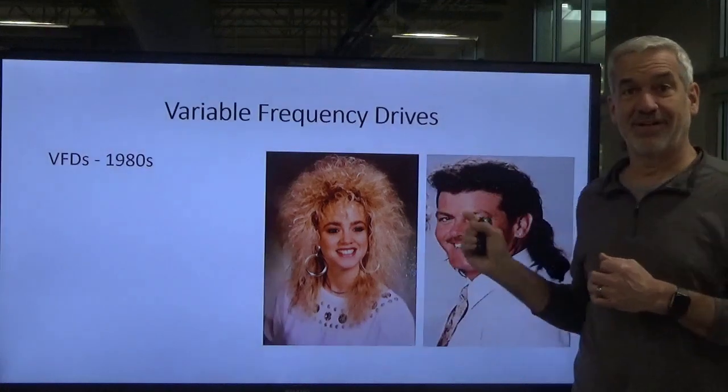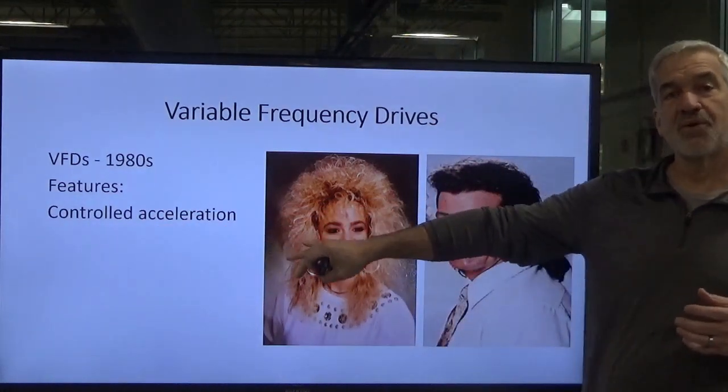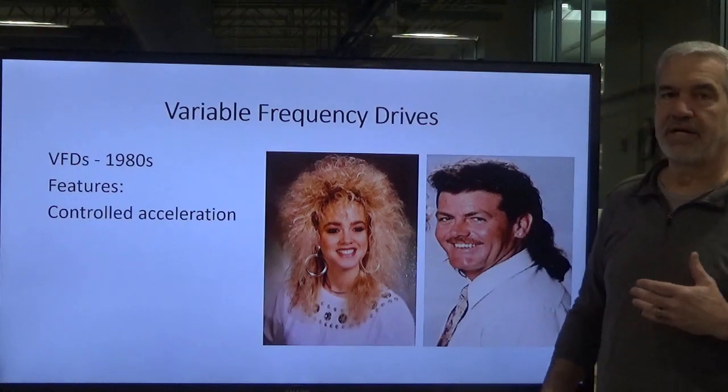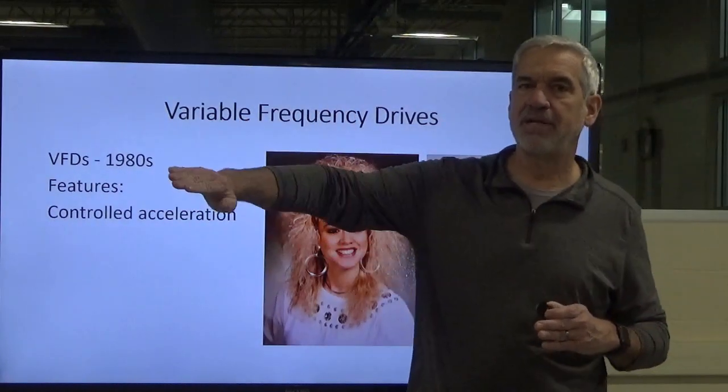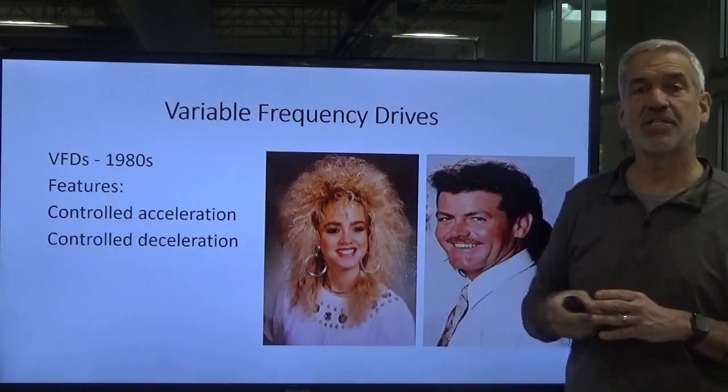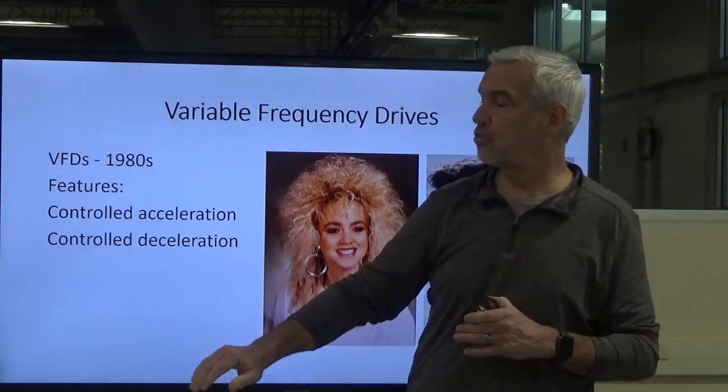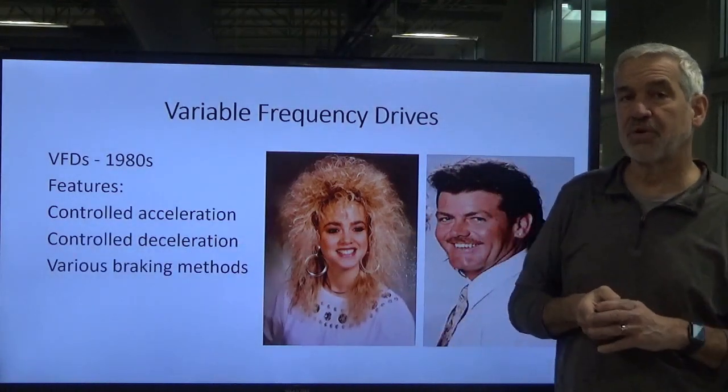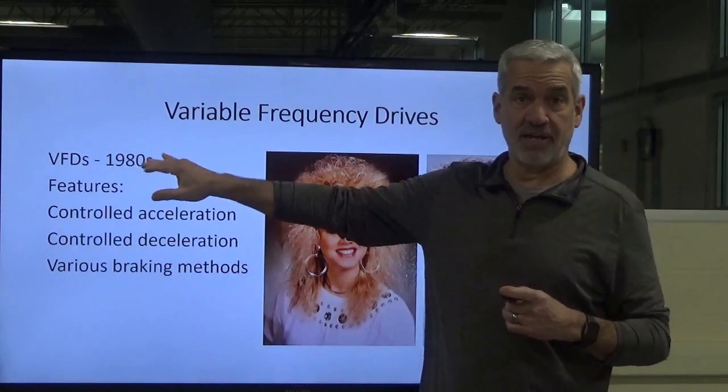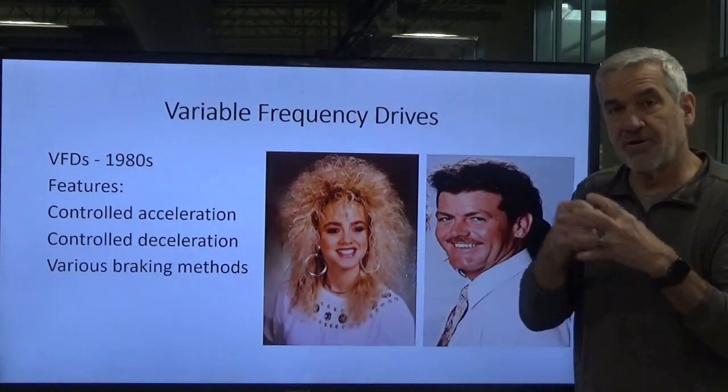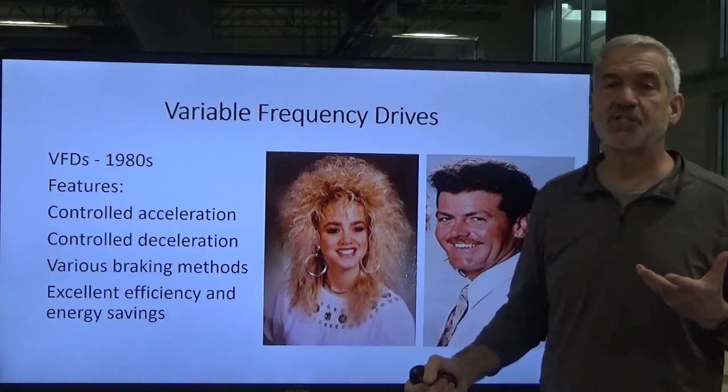Along comes the 1980s and the advent of the VFD. This gave us controlled acceleration, that's our ramp up speed. We could go from zero to full speed over the course of 10, 15, 20, 30, 60 seconds, however long we wanted to ramp from zero to full speed. It also gave us controlled deceleration, going from full speed down to zero. Instead of a flat shut off or hard stop, we could slowly control the deceleration. We had different braking methods. The VFD can add an electrical brake, not mechanical, that we'll talk about shortly.